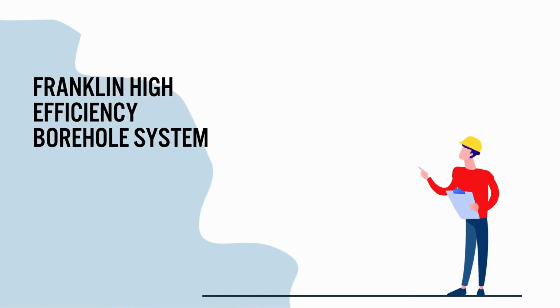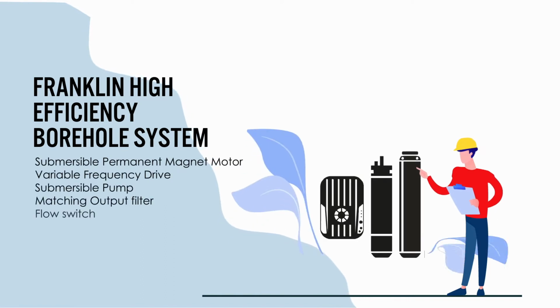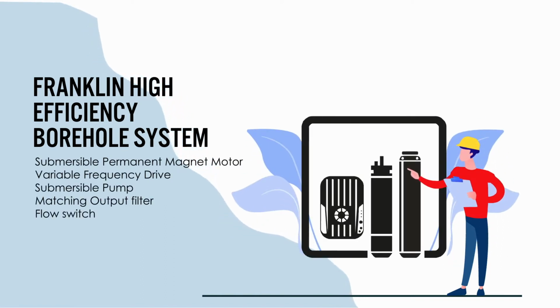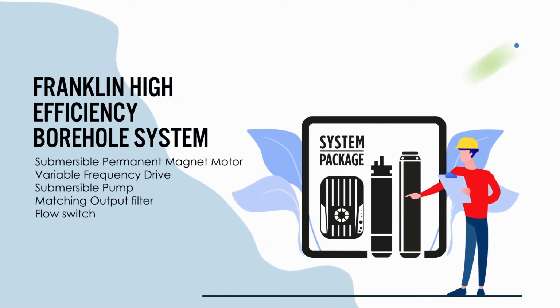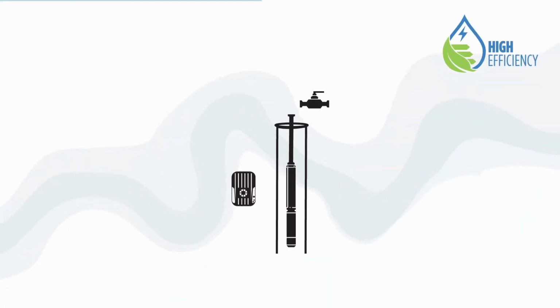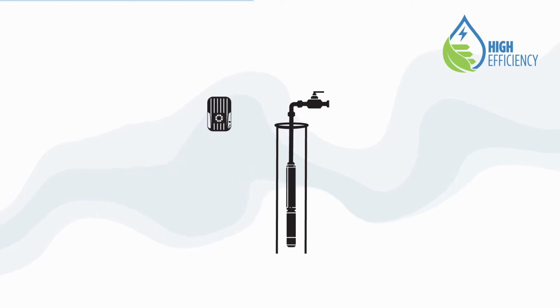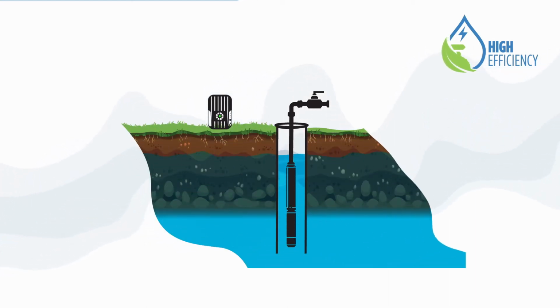The Franklin High Efficiency System, called HESS, includes these perfectly matched components: a permanent magnet high-efficiency submersible motor, a submersible pump, and a frequency converter, matching output filter for systems higher than 230 volt, optional flow switch for solar systems.